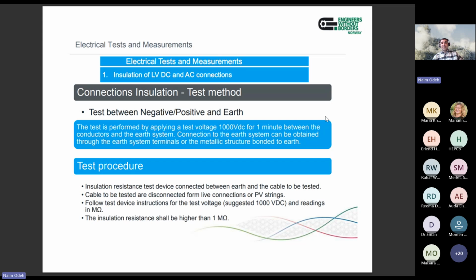This kind of test is important. It is mandatory and highly recommended to be done. But at the same time, it is not recommended to keep repeating it, because continually applying such voltage may affect the connectors and the cables. So in this case, this is not good.